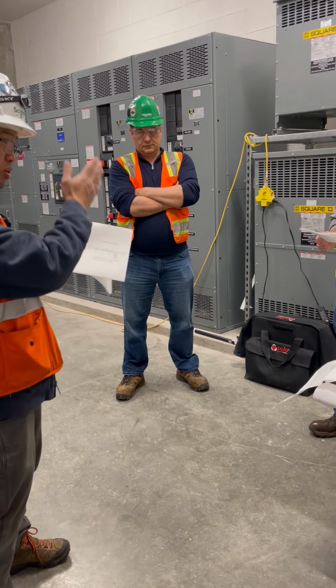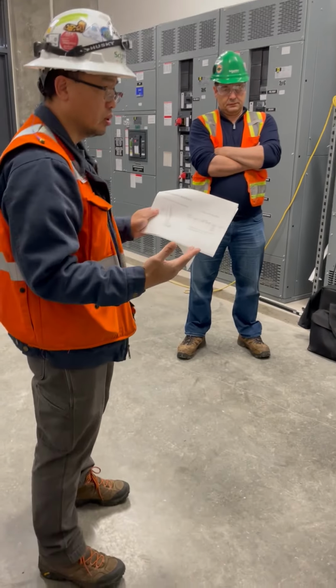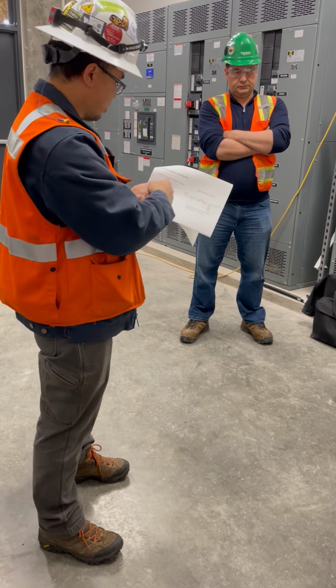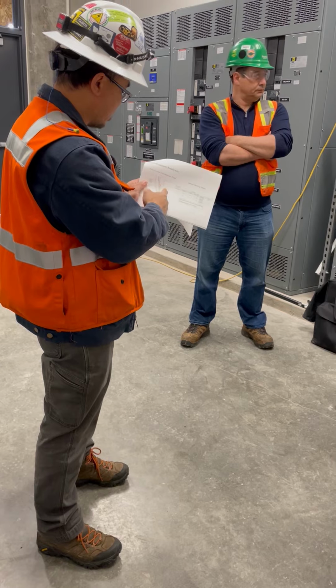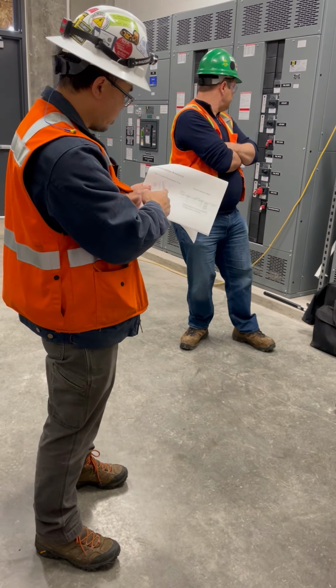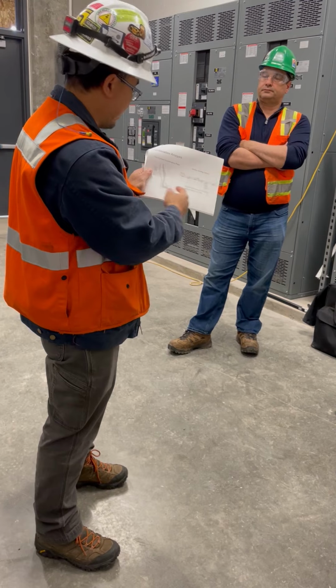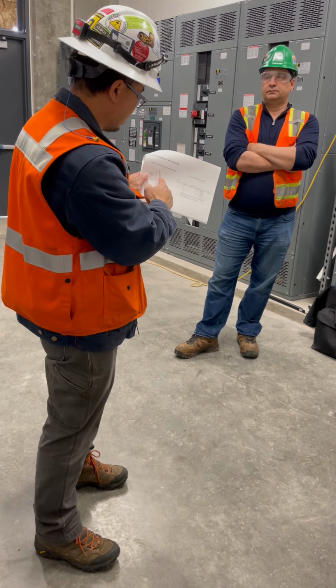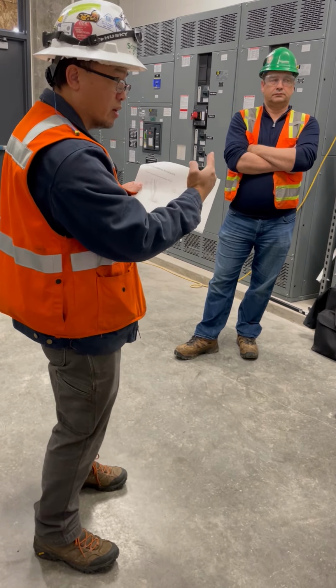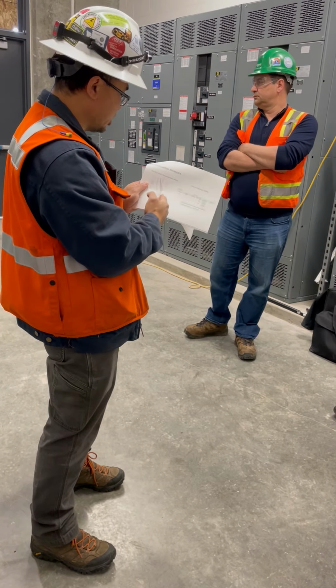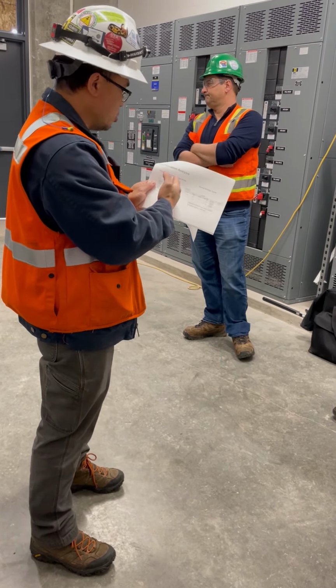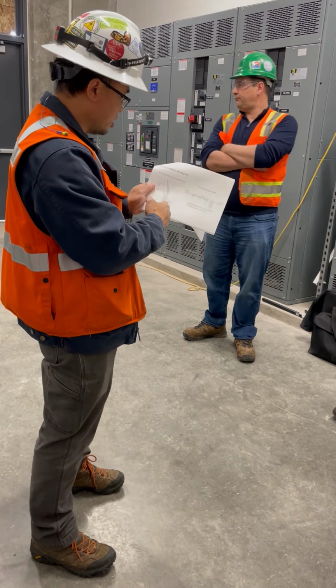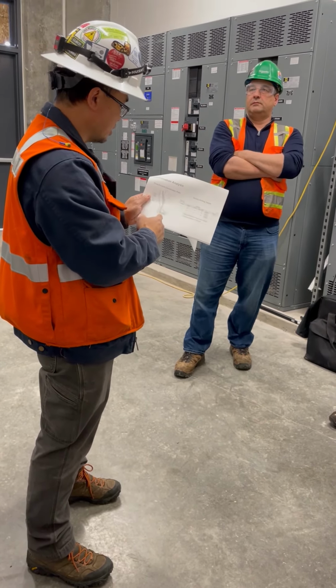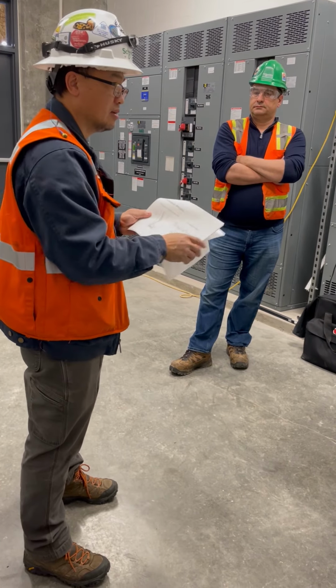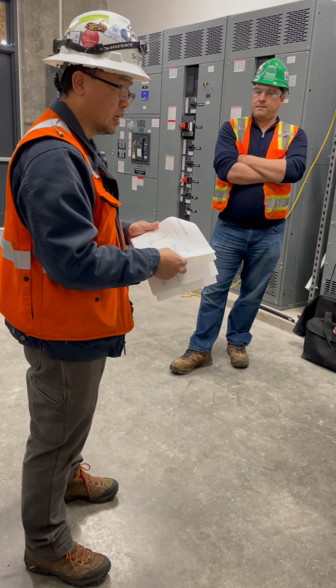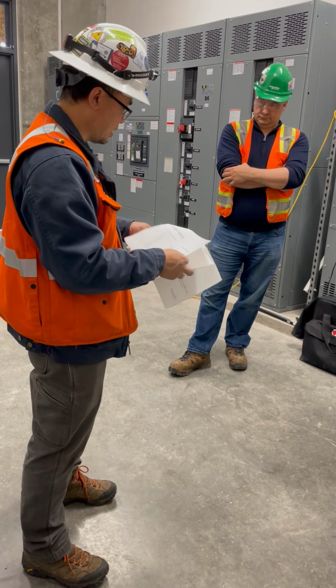Each one of these breakers has its own characteristic, how it operates and responds to current. So as you can see here, this one is fixed. Like this right here, the one on the far right, that's maybe the main breaker. See right here, there's a little bit of overlap, so maybe we move it a little bit to the right to get some coordination if there's a fault in here. Ideally, if you had a fault here, you want this one to trip instead of this one. So there's some overlap here, right? That's why we do the modeling, do the study, and analyze all this data.